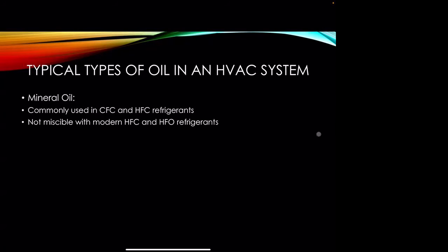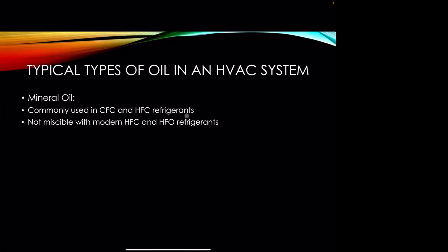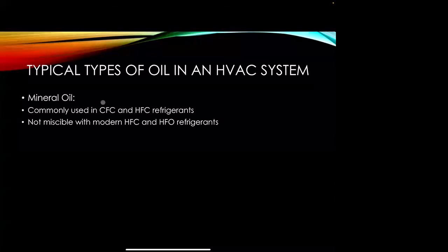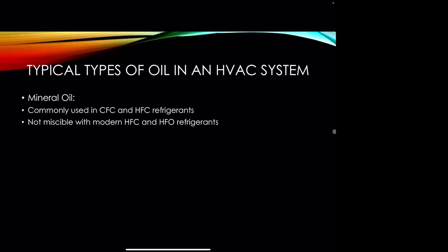What's miscible mean again? How well it blends. How well it blends, exactly. So mineral oil, used in CFCs, R22, is not miscible with our modern refrigerants, which is why when we go from an R22 to an R410A system, we want to replace that line set if at all possible, but clean it if we can't.